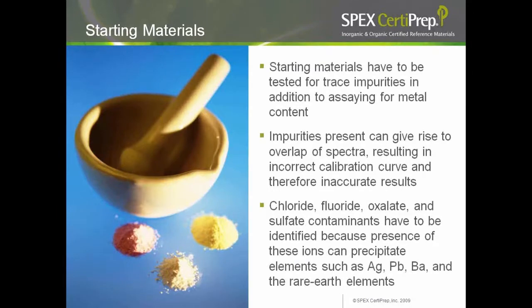The certified reference material — which I will abbreviate as CRM — is made from very high-pure metals. Where such high-pure metals are not available, they are produced from very high-pure compounds. In addition to assaying the metal content before its use in CRM, the starting material should be tested for trace impurities, as these can cause overlap of spectra, producing inaccurate results. Besides trace metal impurities, anions like chloride, fluoride, oxalate, and sulfate contaminants must be identified, because the presence of these ions can precipitate elements such as silver, lead, barium, and rare earth elements.